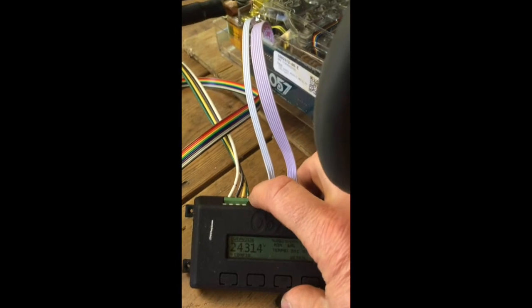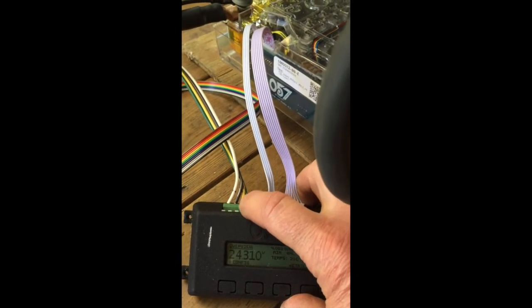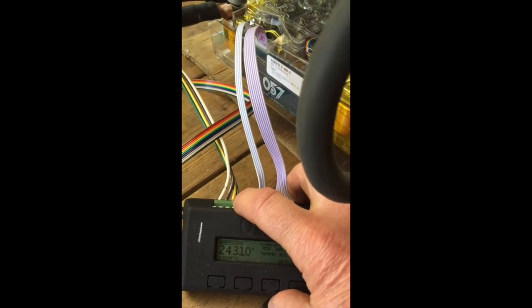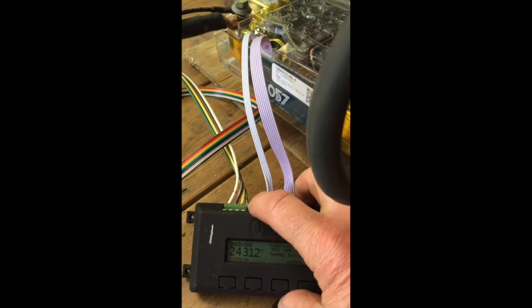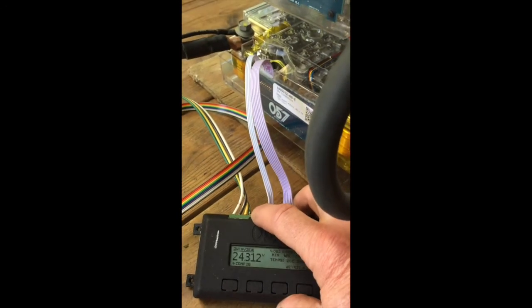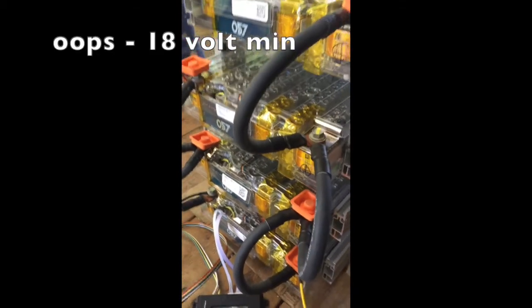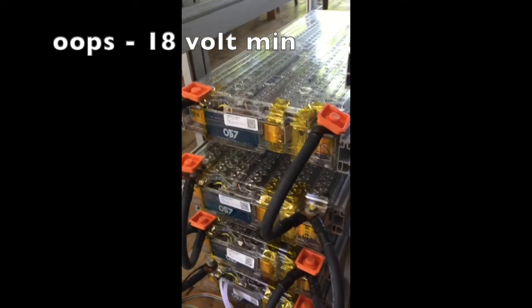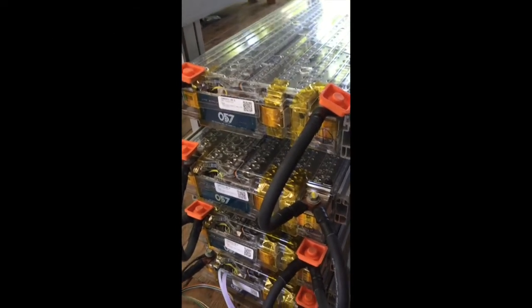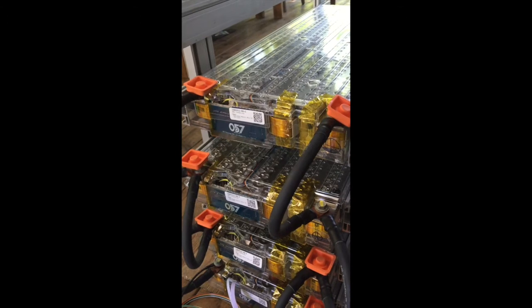The Tesla batteries operate at 24 volts, and the old lead-acid batteries are also 24 volts, but the voltage range between them is quite different. The Teslas operate between about 16 and 25 volts, and a 24-volt lead-acid system operates between about 23 and 30 volts. So all of the charging parameters needed to be reset throughout the system.